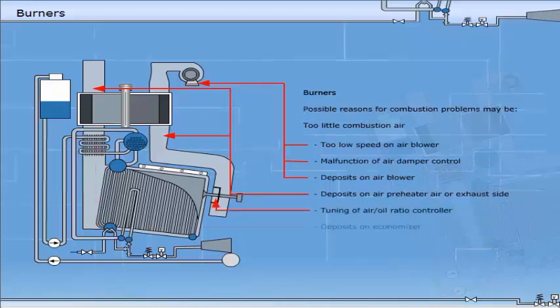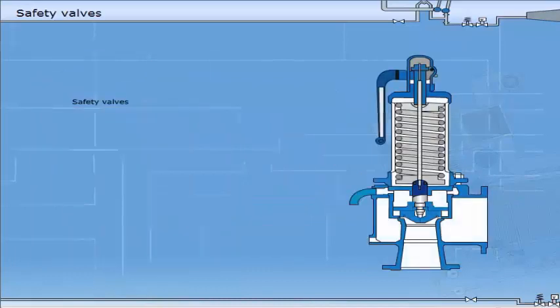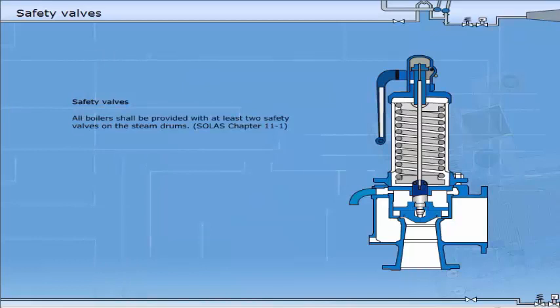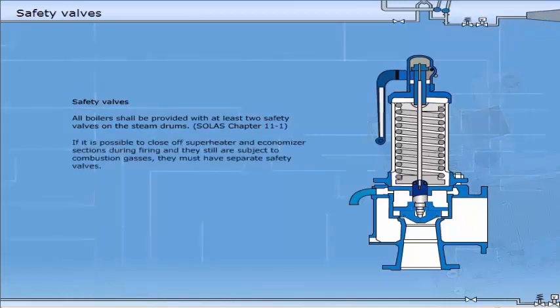All boilers shall be provided with at least two safety valves on the steam drums, SOLAS Chapter 2-1. If it is possible to close off superheater and economiser sections during firing, and they are still subject to combustion gases, they must have separate safety valves.